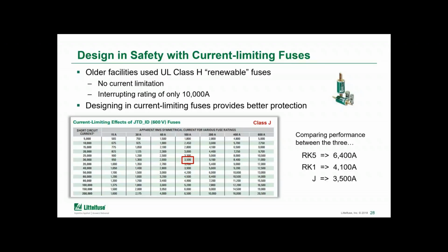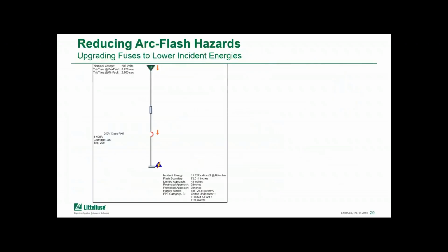So there's certainly a lot of options that the design engineer has, and in the end, reducing that opening time can help to mitigate the potential arc flash magnitude, provided that the fuse curve meets the reliability requirements. Just to put this into a single line diagram, if we think back to the hierarchy of controls, we're again talking about the effectiveness of substitution. This is a really quick example of how substituting one fuse type for another, in this case upgrading RK5 to RK1 fuses, can have a pretty substantial impact in mitigating the arc flash hazard.